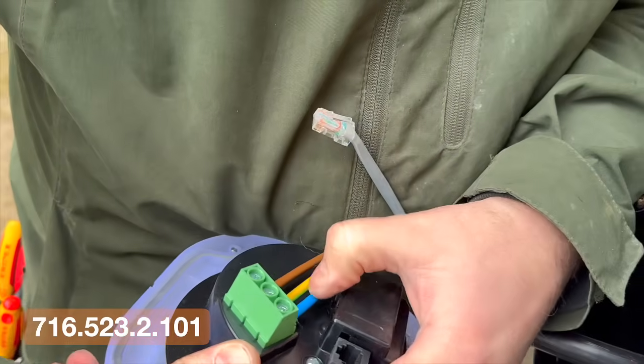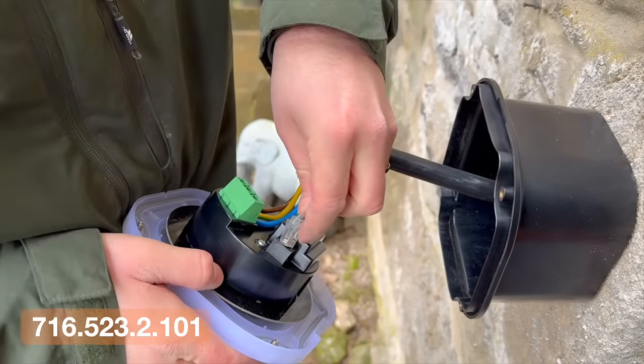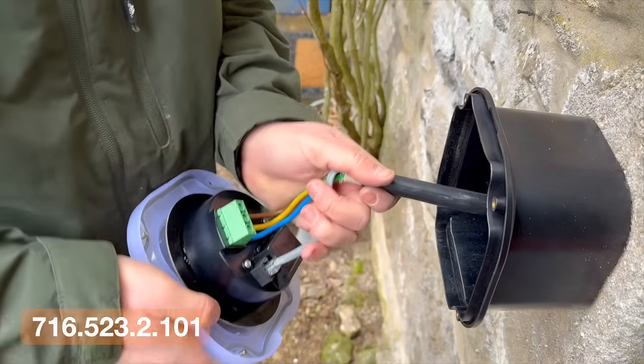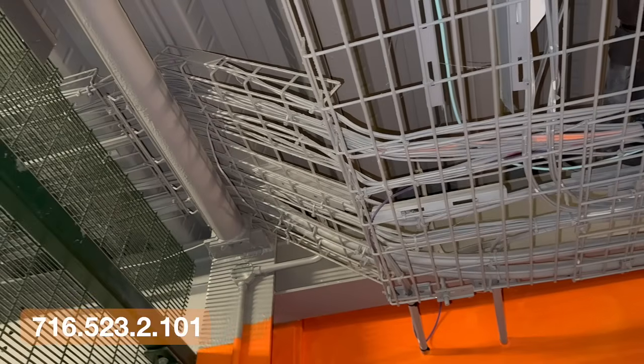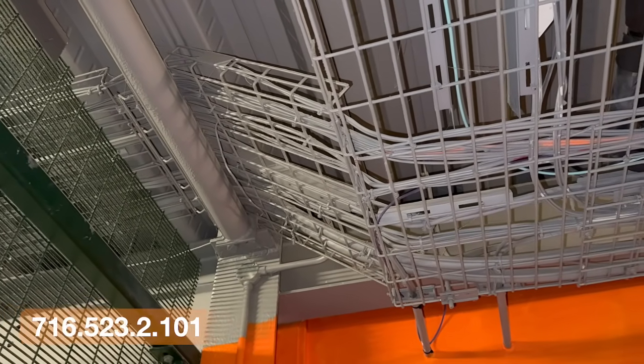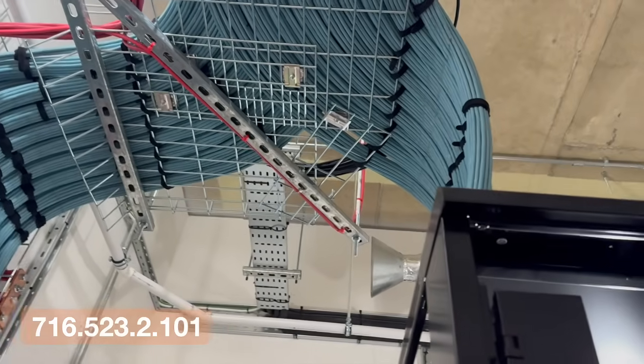Regulation 716.523.2.101 limits the current in each conductor to 750 milliamps. That might not sound like a lot, but when you group multiple cables together, that heat starts to build up. And that has a direct effect on both safety and performance. As the temperature increases, you can get higher attenuation, which means the data performance of the cable can start to degrade. So how you install these cables now matters far more than it used to.